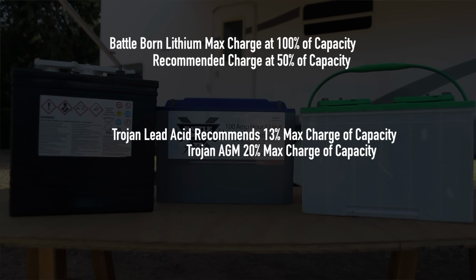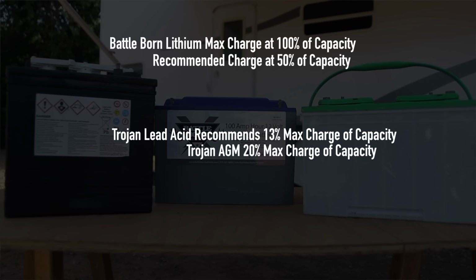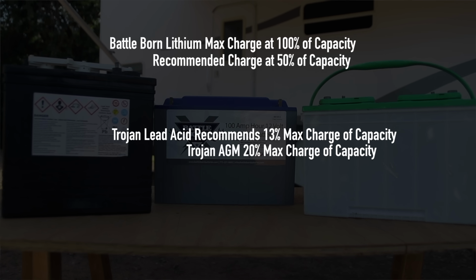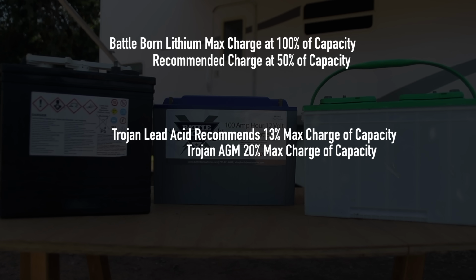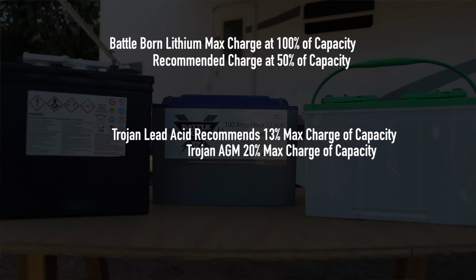Now, a lithium battery, the Battleborn one that we're using for reference, you can charge at a 1C rate. So if it's a 100 amp hour battery, you could charge it at 100 amps, but you will be reducing the abilities of the battery in the long run. The lifespan of that battery is not going to be as good. So technically, yes, you could, but to extend the life of the battery, you want to charge it at half of that C rate. So it can take 50 amps rather than 100 amps to safely charge it, without doing damage to the battery.